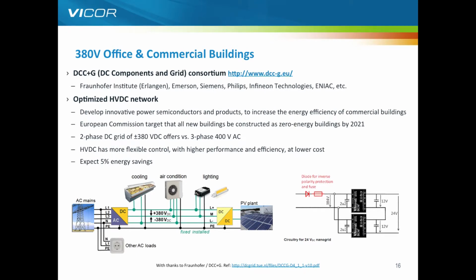The diagram on the bottom left shows how plus or minus 380 volts around a middle point can provide varying voltages, either 380 or 760 volts, to different DC loads, or if there are legacy systems requiring AC, you can have some very low power AC lines running around the building. This helps because, as well as AC mains coming from the left-hand side, you can also have photovoltaic from the right-hand side, making a small microgrid.